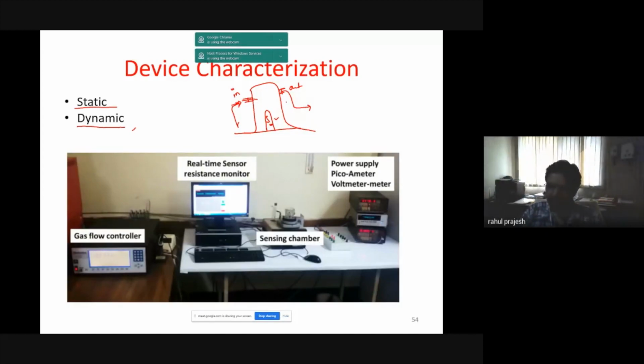So these are the typical categories of the measurement. If you see a typical sensing chamber, this may be very useful if you are working in this particular area. You have a sensing chamber, and this sensing chamber is connected with pipelines to the MFC controller. This is the mass flow controller. In this mass flow controller, we have 4 MFCs.